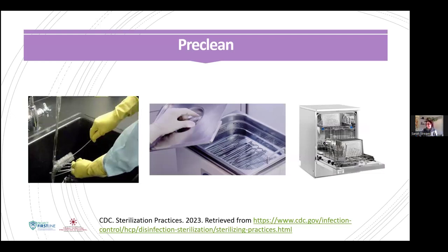When we get to our pre-cleaning area in sterilization, there are a couple different ways we can pre-clean our instruments. So there are automated ways, and then there are the hand scrubbing ways. And we want to lean toward the automated ways because they take our hands out of that cleaning equation and reduce the risk for exposure incidents. So our automated methods would be our ultrasonic cleaners and our washer disinfectors. And each of those, they'll have their own IFUs. They'll both have chemical solutions that should be used with them. And those IFUs specific to the machines, the equipment, and the chemicals should be followed.